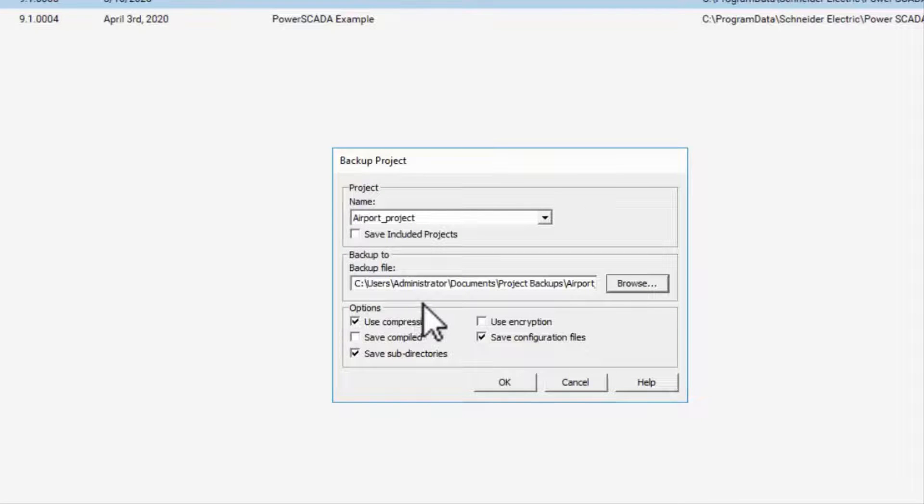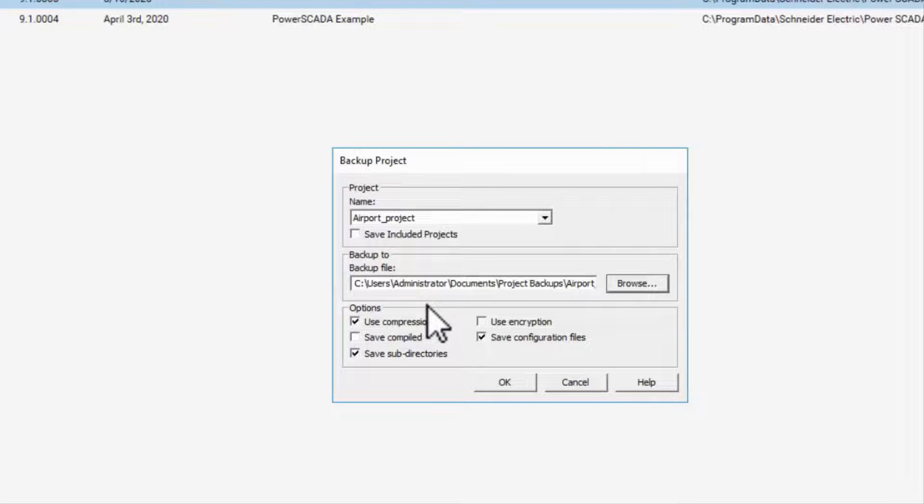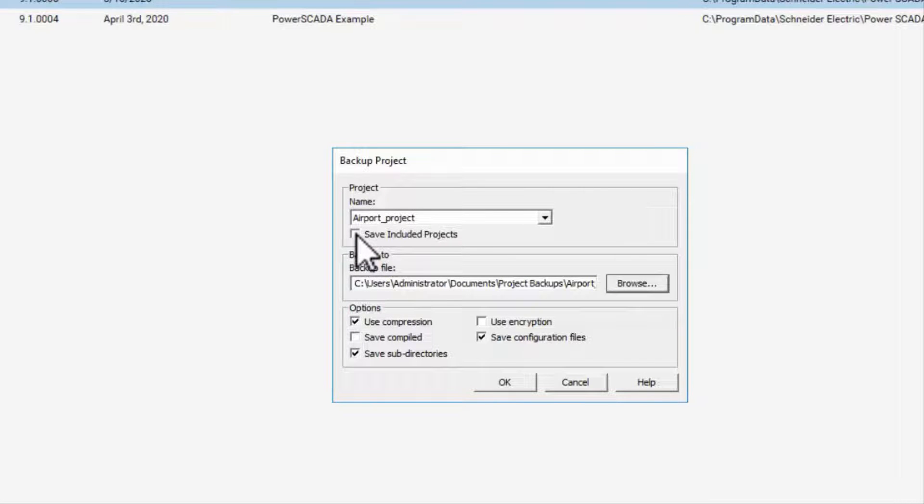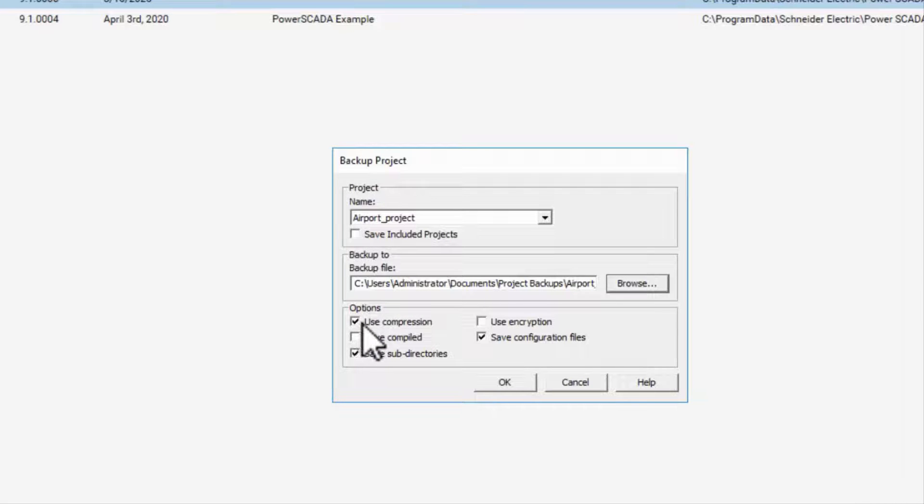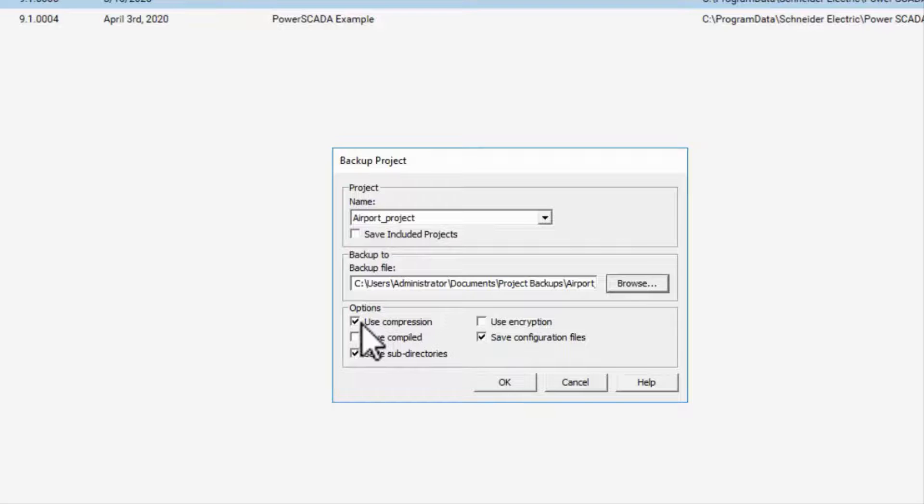PSO backup only includes the project and not the data. The Include Projects option should be saved if you are creating a full archival backup but can be turned off for day-to-day backups to save space. If you use compression, the backup is in .ctz or CitectSCADA zip format, which can be changed to .zip and opened in Windows.